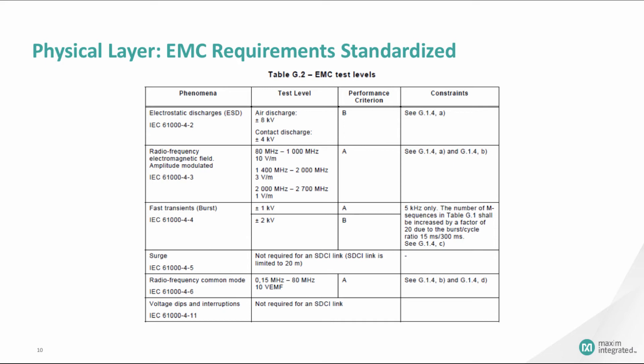Industrial environments are harsh and require special considerations. The IO-Link standard sets a minimum EMC (electromagnetic compatibility) performance requirement to ensure devices can withstand common transient issues. For example, ESD requires ±8 kilovolts for air discharge or ±4 kilovolts for contact discharge, based on the IEC 61000-4-2 standard.